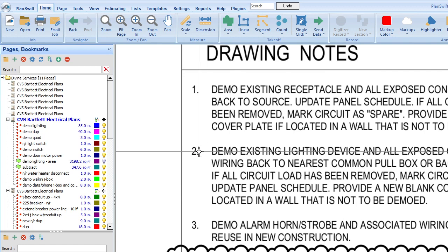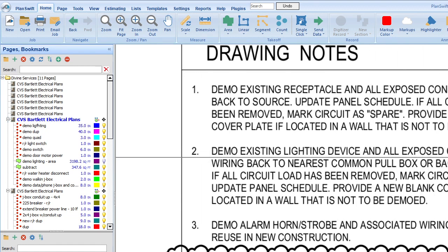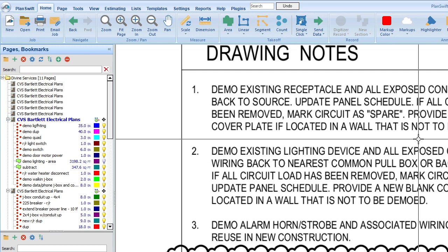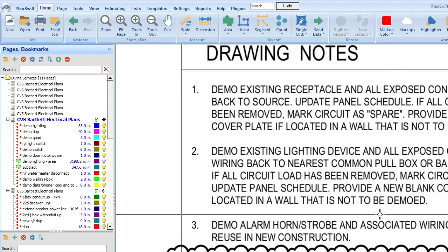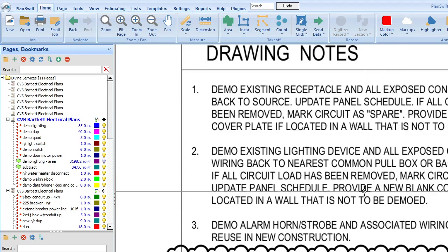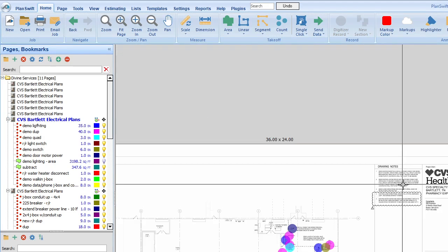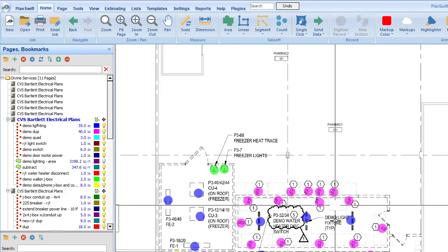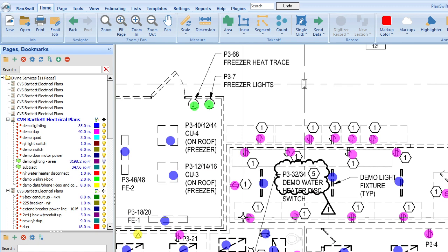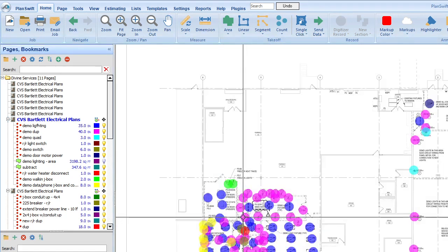All right. So we'll go back. So demo existing receptacle and all exposed conduit and wiring back to source. Update panel schedule. If all circuit loads have been removed, mark circuit spare. See, that's all a part of balancing that. Blank cover plate. Demo existing lighting device. So we've got the wiring devices, so the outlets and receptacles. And then number two, demo existing lighting device and all exposed conduit to wiring back to nearest common pull box or back to source. Now, we have an issue when it comes to this.